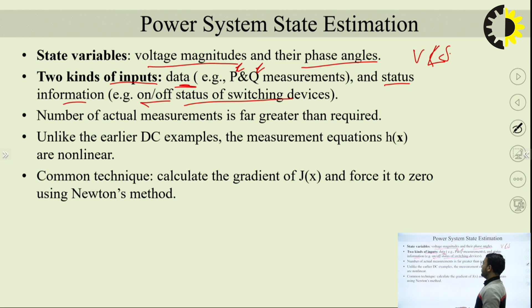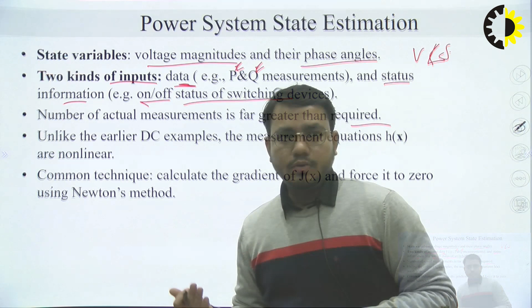Now the number of actual measurements is far greater than required. If you have to do state estimation in the power system, the number of actual measurements must be far greater than required, because you will have bad data in the actual readings, and you have to reduce or strike out the redundant, bad data from the available data.